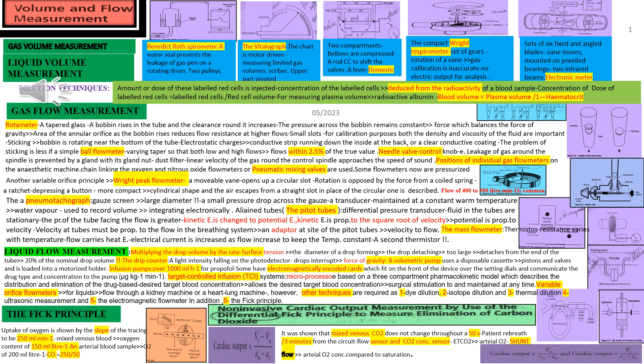In this system we have the opportunity that if we rebreathe for 30 seconds, not much change will occur in the mixed venous blood carbon dioxide. This is the method to create two cardiac output equations. So whenever these two cardiac outputs are joined together, whether the patient is normally non-rebreathing or rebreathing after closing this valve, we can create the cardiac output figure by noting the flow of carbon dioxide in rebreathing minus the flow of carbon dioxide in normal non-rebreathing, over the arterial carbon dioxide in non-rebreathing normal minus arterial carbon dioxide in rebreathing. So this is the difference. We are subtracting the smaller from the bigger one.